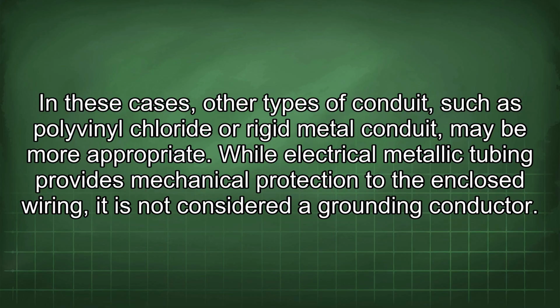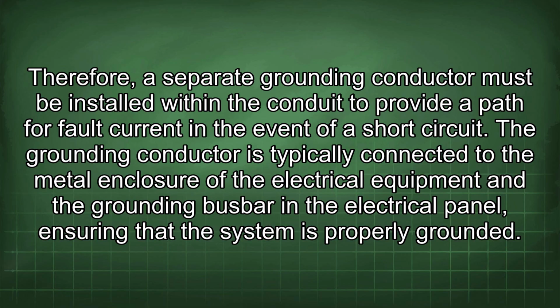While electrical metallic tubing provides mechanical protection to the enclosed wiring, it is not considered a grounding conductor. Therefore, a separate grounding conductor must be installed within the conduit to provide a path for fault current in the event of a short circuit. The grounding conductor is typically connected to the metal enclosure of the electrical equipment and the grounding busbar in the electrical panel, ensuring that the system is properly grounded.